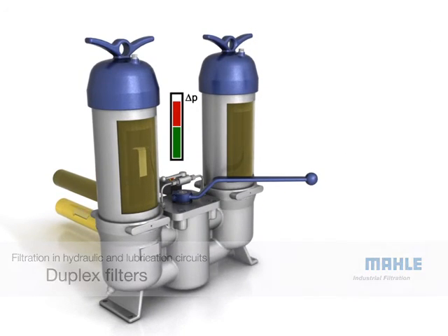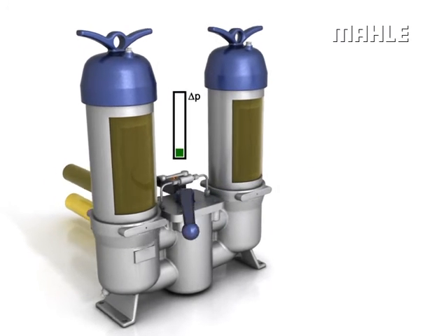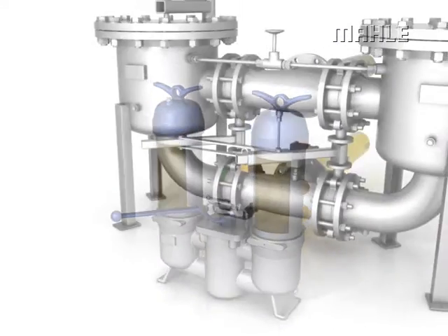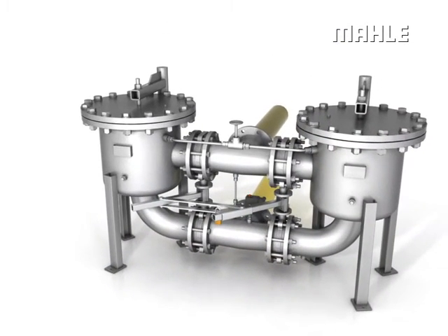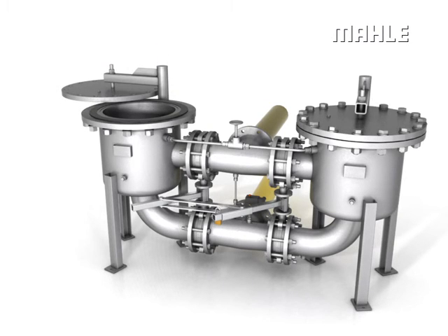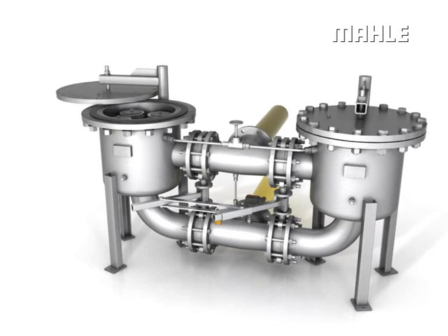Duplex filters, equipped with a standard maintenance indicator, are ready for duty 24 hours a day, thanks to a switchover feature that allows the filters to be serviced in continuous operation. Modern systems operate with elements that can be removed from the top. With their high flow rates, duplex filters are designed for economical as well as ergonomic maintenance and operation.